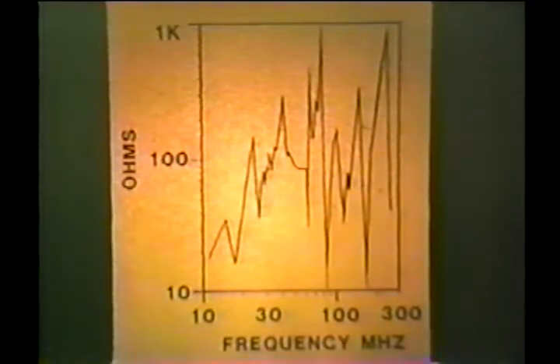And of course, if you put all of these together, you can end up with a rather complex curve. In this case, this is the impedance of an entire circuit on the 140 MVA machine. It consists of 28 stator bars, 2 groups of 6, 2 groups of 8, and has well over a dozen resonant points between 10 megahertz and 300 megahertz. Each one of the resonant points indicates oscillation of a stator bar, end arms, phase rings, or combinations of those.